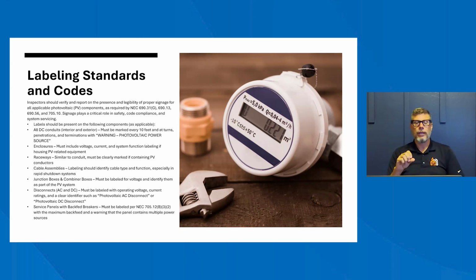It's going to say warning, inverter output connection, do not relocate overcurrent device. That's the one that's located in the bottom right of your electrical panel. And that's the standard, that's where they put it. If you see it someplace else, you may want to question who put it in the system. And then if you have a rapid shutdown, it's going to say rapid PV system equipped with rapid shutdown right next to the rapid shutdown, and it's usually just a dial each turn.